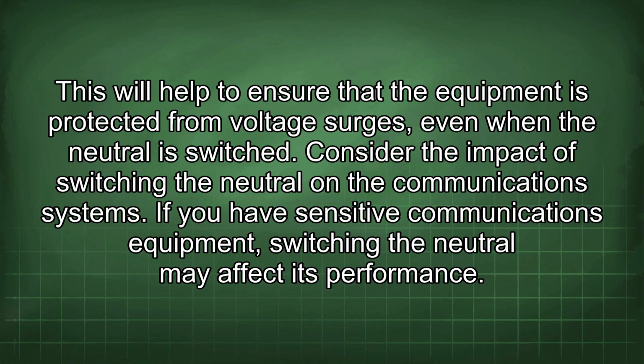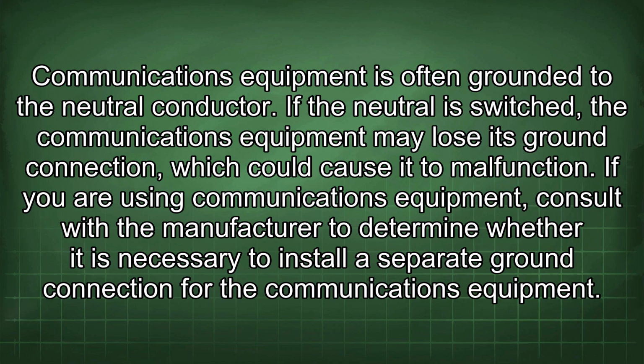Consider the impact of switching the neutral on the communications systems. If you have sensitive communications equipment, switching the neutral may affect its performance. Communications equipment is often grounded to the neutral conductor. If the neutral is switched, the communications equipment may lose its ground connection, which could cause it to malfunction.